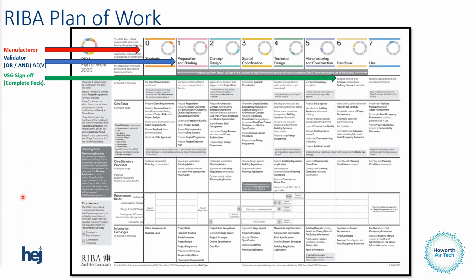And then obviously the ventilation safety group, they will also be part of every single stage. The authorising engineer for vent would be part of that safety group, but then they go on from handover and into clinical use. The reason that I put the complete pack there below the ventilation safety group is because I've seen systems where it's just been commissioned and not independently validated afterwards. Then it goes into clinical use with issues from a mechanical point of view later down the line. So it's got to be a complete holistic approach and look at the system.